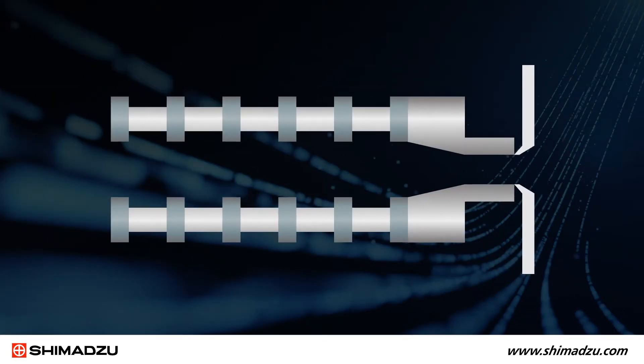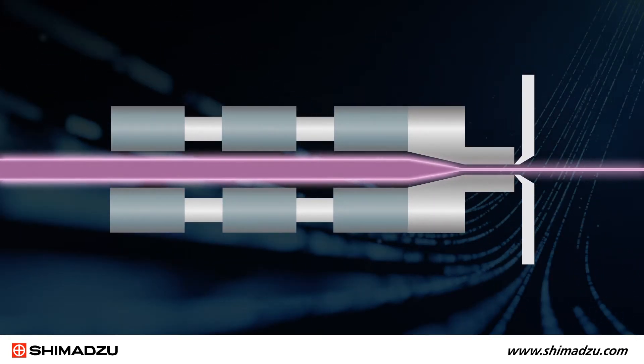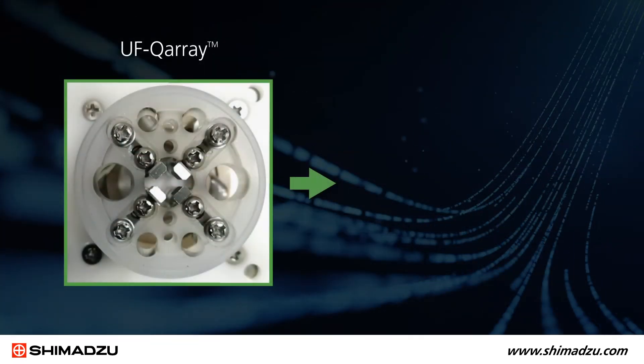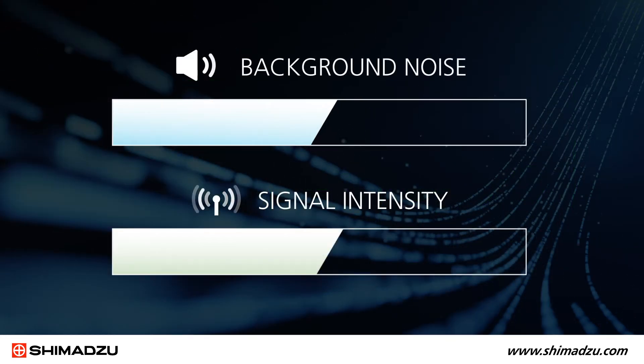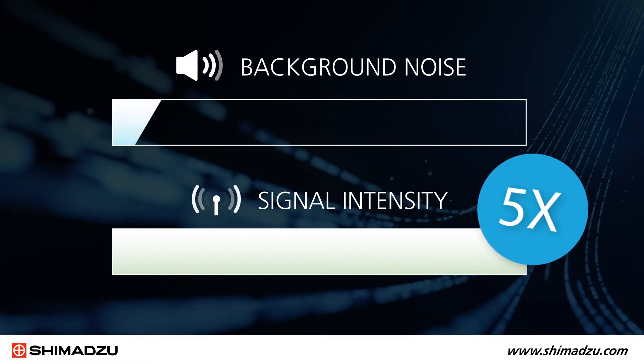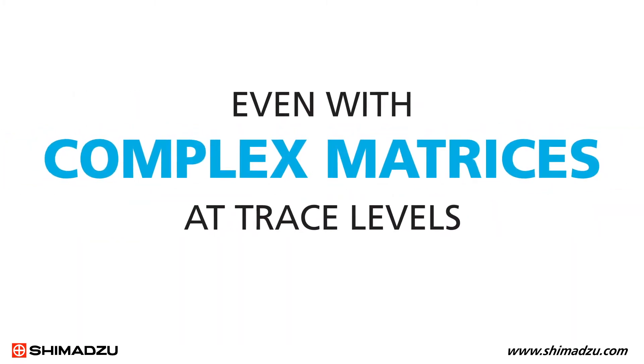For this design, we opened up the ion inlet and narrowed the aperture at the end of the array. This converges the ion beam precisely into the quadrupole mass analyzer. The wider gas flow path ensures that inert particles do not interfere with the ion path. Background noise is reduced while signal intensity is increased up to five times. This unique approach routinely delivers robust detection at very high sensitivities, even with complex matrices at trace levels.